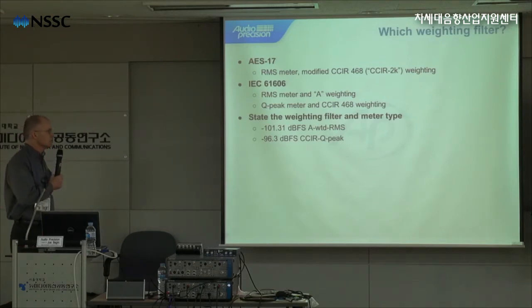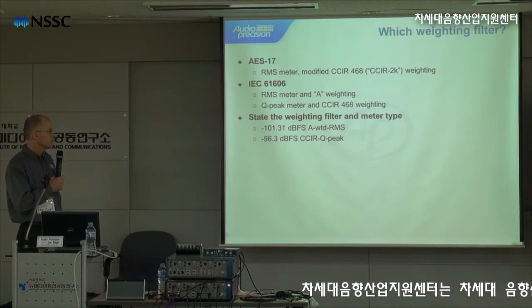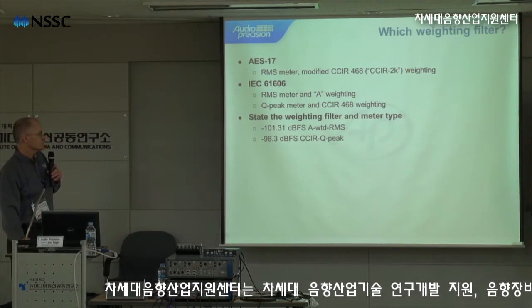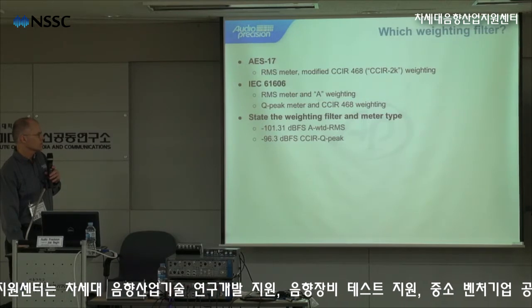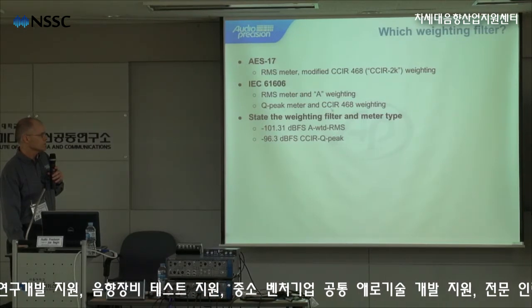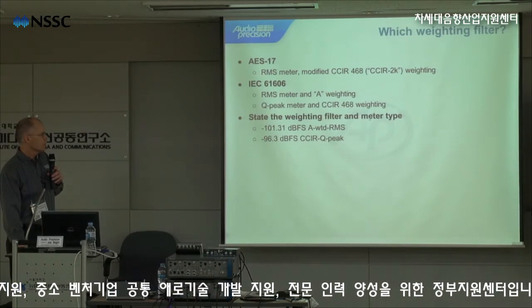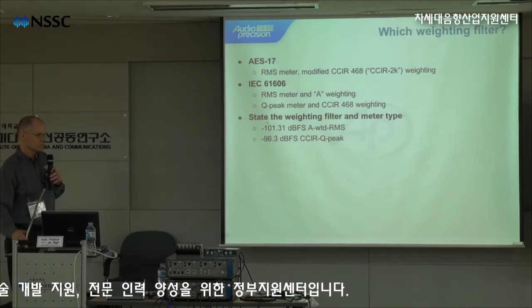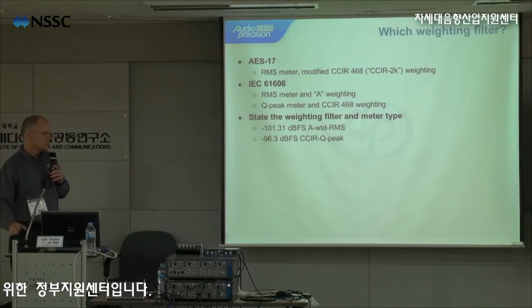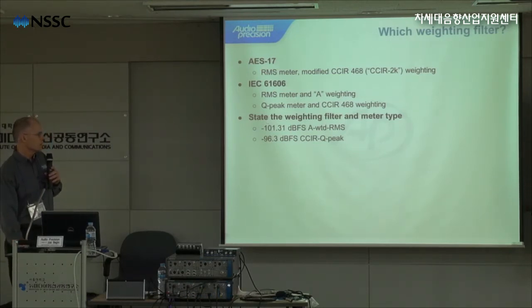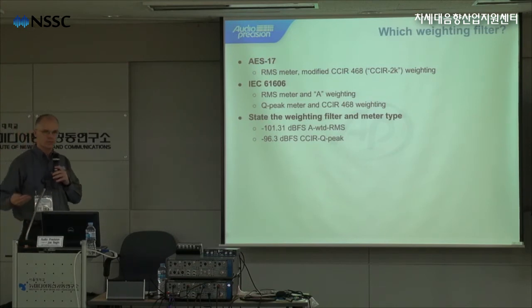So AES-17 uses an RMS meter with a modified CCIR 468 or CCIR 2K weighting filter. IEC 61606 uses an RMS meter with A weighting and a Q-peak meter with CCIR 468 weighting. Again, when you're quantifying a noise measurement, it's important to state the weighting filter and the type of measurement, whether it's Q-peak or RMS. If you don't use a weighting filter, of course, you should specify the bandwidth of the noise measurement.